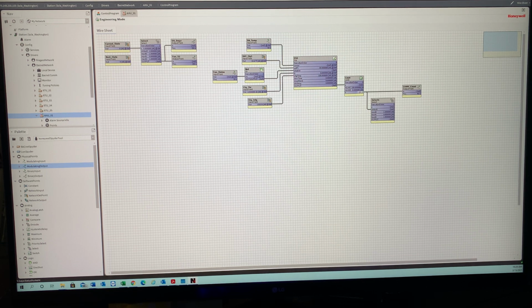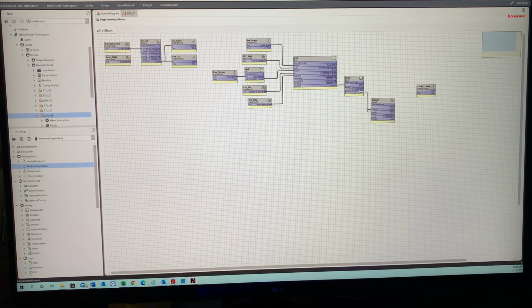We want to go into default, and then we want to go into 0. There's probably, let's say, 10 different ways to get to the same product. What I'm trying to do is give you guys real basic information and then build upon it, get your own unique style, and do what works for you. So I'm going to delete this link to the chill water valve command. Here we have our default and our 0. So basically, when the humidity is not being called for any kind of control, it'll be controlled based on our discharge air temp PID.